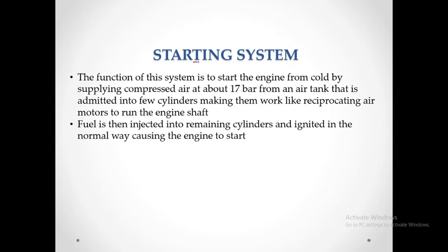Okay, so what does the starting system do? The function of the system is to start the engine from cold by supplying compressed air at 17 bar from an air tank, which is admitted into a few cylinders, making them work like reciprocating air motors to run the engine shaft.